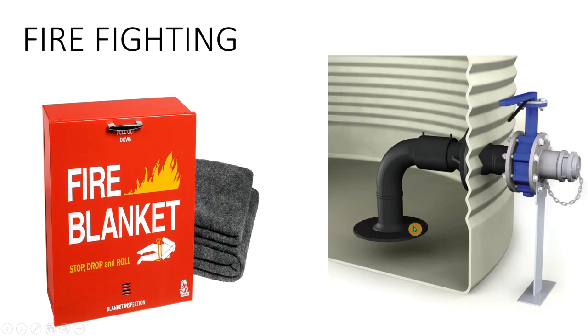As you can see, this is the anti-vortex plate. This anti-vortex plate is placed inside a tank. Mostly this will be placed inside a tank. So when the pipe runs inside your tank, the end of the pipe, or else the beginning of the pipe from the tank, should be welded or else connected with this anti-vortex plate. This will help you to eliminate the swell or else the suction surge in your tank. So the anti-vortex plate is also mandatory when it comes to tank and pipe connection.